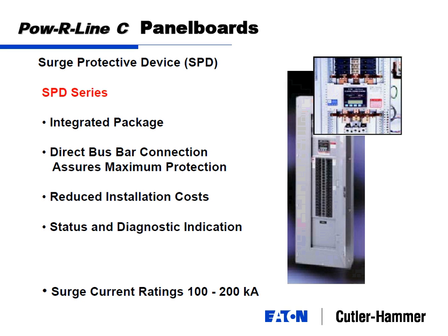One of the options that you can put in lighting and receptacle panels, as well as any panel boards for that matter, is the surge protective device. The SPD series is our new one. Now, I've got the old one here. This is the Clipper series. About a year and a half ago, maybe actually a year ago, it went into effect: UL changed all their test requirements, and as part of their whole change, what used to be called TVSS, transient voltage surge suppression, they threw that whole category out and called it SPDs, or surge protective devices.